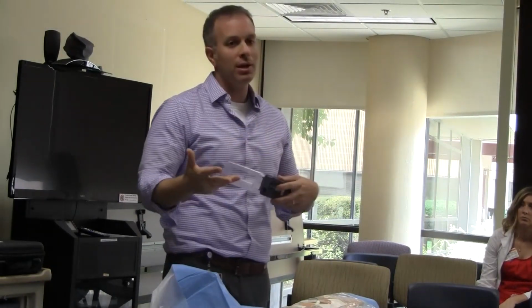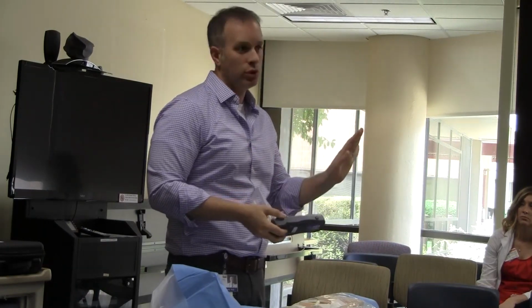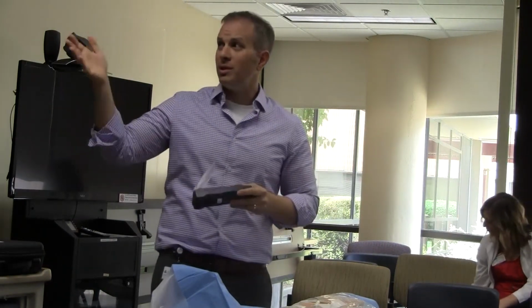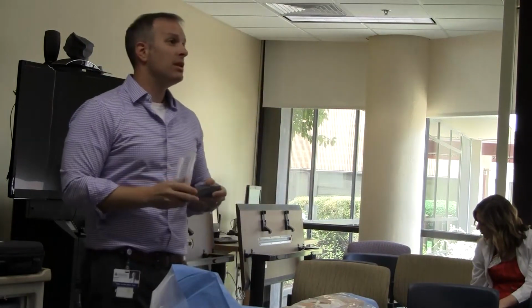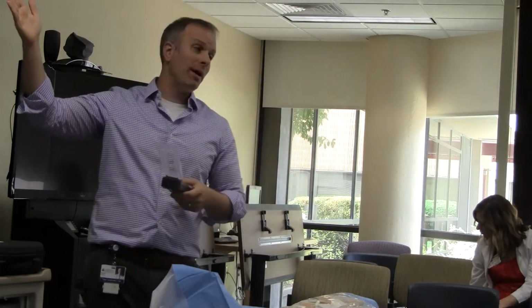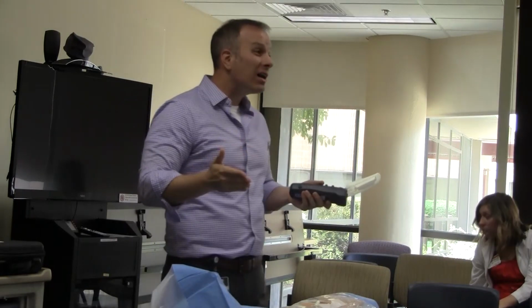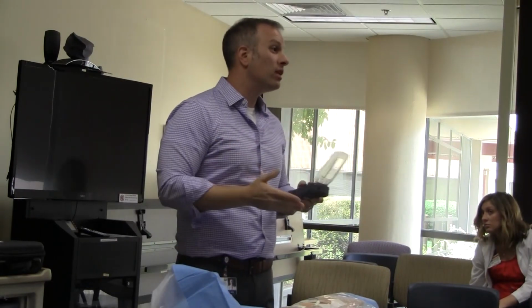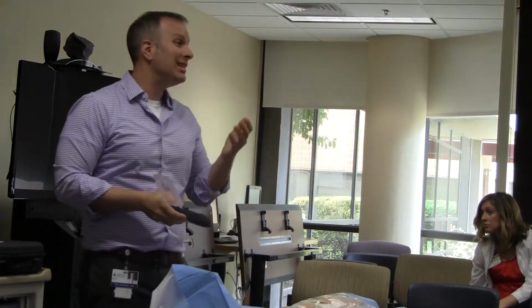It gets a lot more complicated to start doing that if you're not familiar with EP. So I usually tell people just leave it at 2 millivolts. That's usually good enough. To give you an idea, when we put these in the lab, the numbers that we're usually getting for how big that spike is are usually 5, 7, 9, 10, those numbers. So if you've got this set at 2, you should easily be able to see a spike, basically.